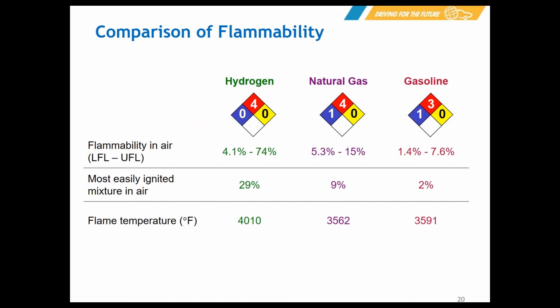A couple of points on this slide: the safety systems employed for hydrogen are able to detect and alarm a gaseous leak at levels much lower than the lower flammability limit of 4.1%. So while we don't want a hydrogen leak, should one occur, gas sensors used in vehicles, stations, and repair facilities would detect and alarm at levels around 10% of that LFL, about 0.4% hydrogen in air.